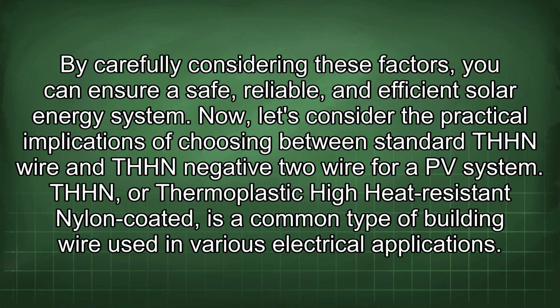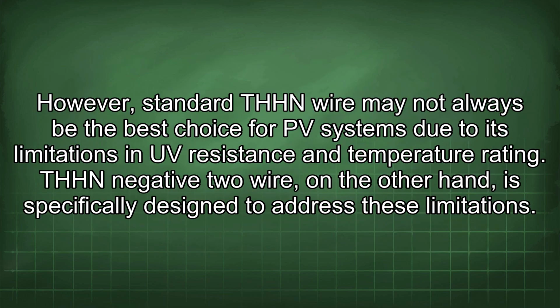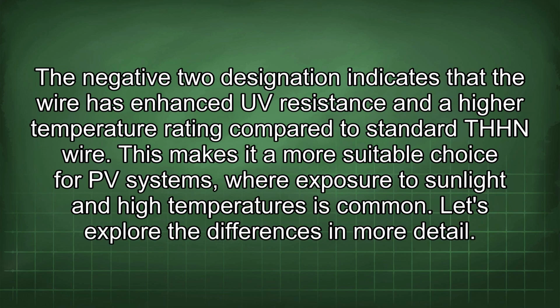Now let's consider the practical implications of choosing between standard THHN wire and THHN -2 wire for a PV system. THHN, or thermoplastic high heat resistant nylon coated, is a common type of building wire used in various electrical applications. However, standard THHN wire may not always be the best choice for PV systems due to its limitations in UV resistance and temperature rating. THHN -2 wire, on the other hand, is specifically designed to address these limitations. The -2 designation indicates that the wire has enhanced UV resistance and a higher temperature rating compared to standard THHN wire. This makes it a more suitable choice for PV systems, where exposure to sunlight and high temperatures is common.